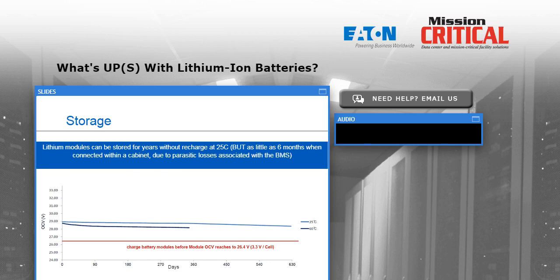The other thing to keep in mind: based on regulations and requirements from UN 38.3, when we ship these batteries as an industry, they need to be shipped at about 30% state of charge, not fully charged. Why? It dramatically reduces any chance of a thermal event during shipping, which is good. But if a battery is shipped to my warehouse at 30% state of charge, its open circuit voltage starts off a lot closer to the red line limit, and that alone severely limits the amount of storage time I can get.